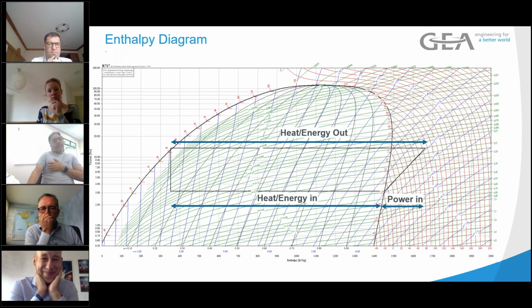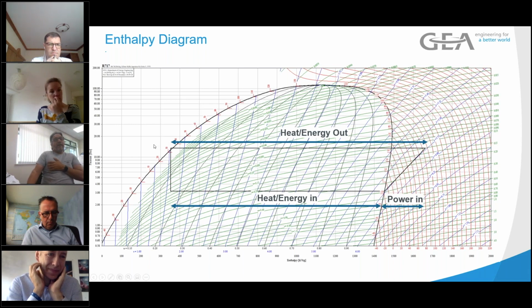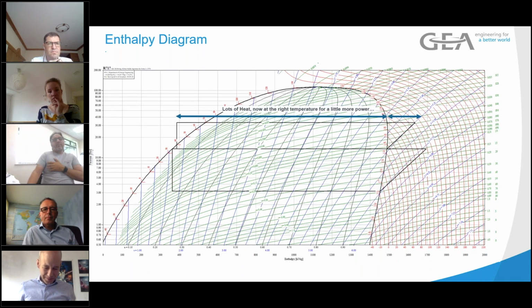So if we have a look at an enthalpy diagram, we have the heat going in at the cold end. We have the power going into the compressor to raise the pressure and condensing pressure. Then we reject the heat at around about 30 degrees or whatever our ambient is, but it's still heat. You know, I always tell our clients that heat's heat, whether it's -40 or if it's 140, it's all energy. So what we do now, we add the compressor, which is boosting that heat to a useful temperature. So now we've got it up to 70 degrees, so we can actually start using it for doing things, pasteurization, this sort of thing.